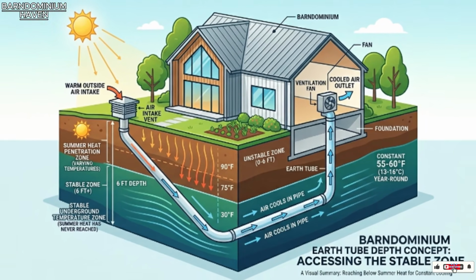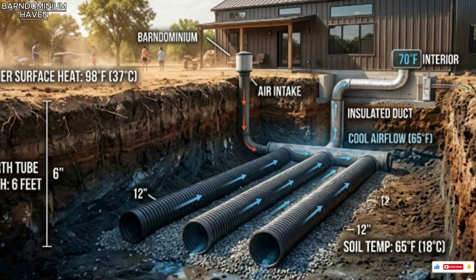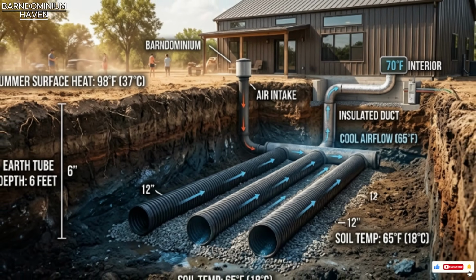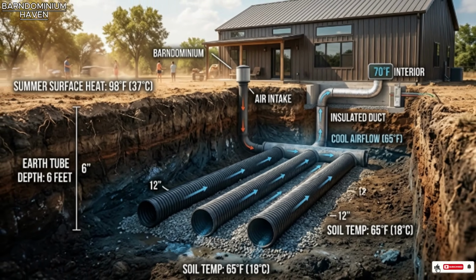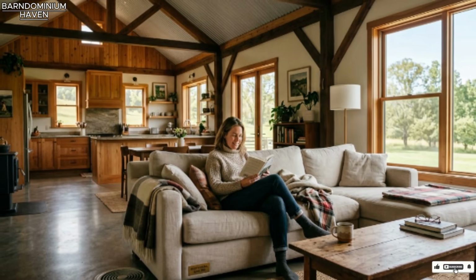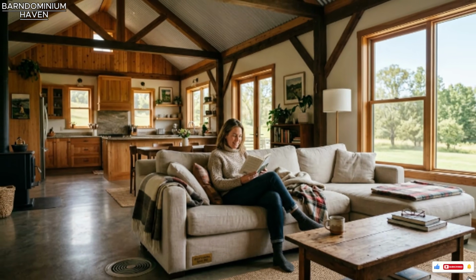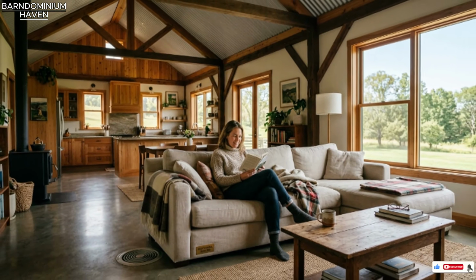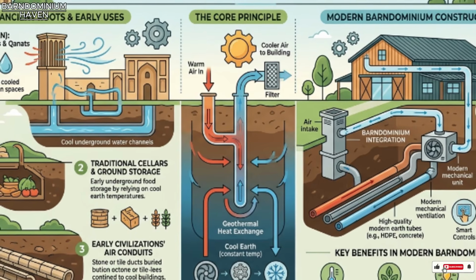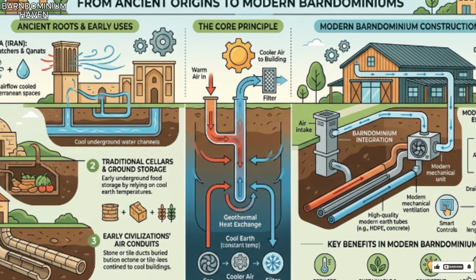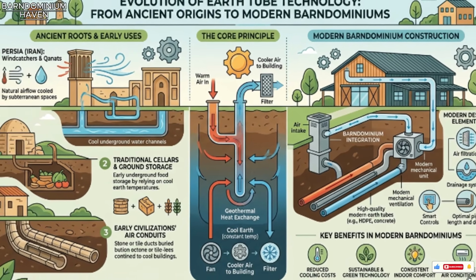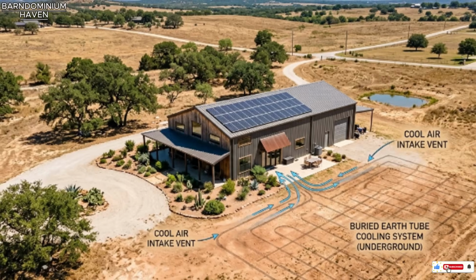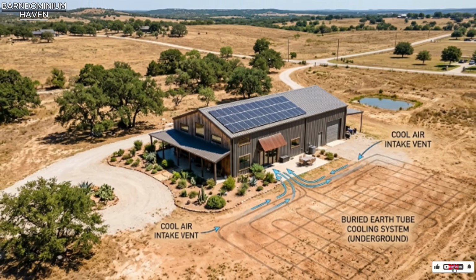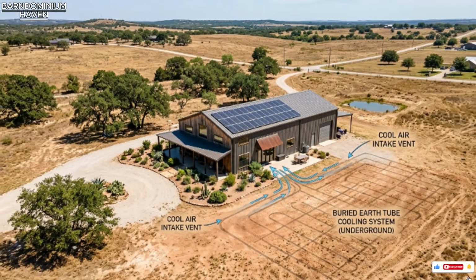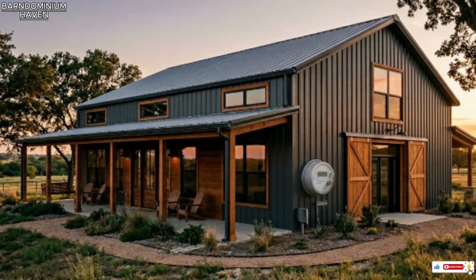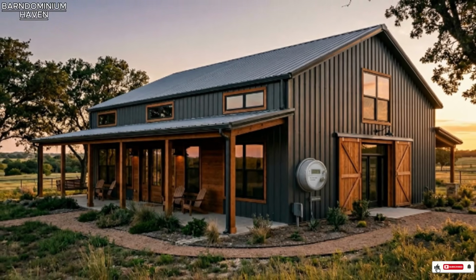The earth tube is the most literal expression of the second relationship available in residential construction. It does not fight the summer heat. It goes underground, 6 feet below it, to where the summer heat has never reached. And brings that depth's permanent coolness back to the surface through a pipe, at the cost of a fan, for $5 a month. That is not a clever technology. That is an ancient truth. The ground is cooler than the air. Finally being applied to the buildings that have been paying to ignore it for decades.